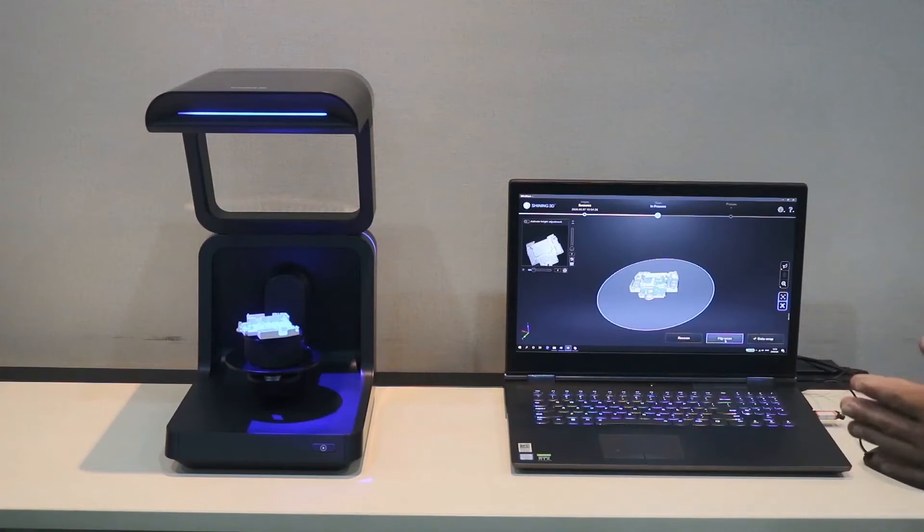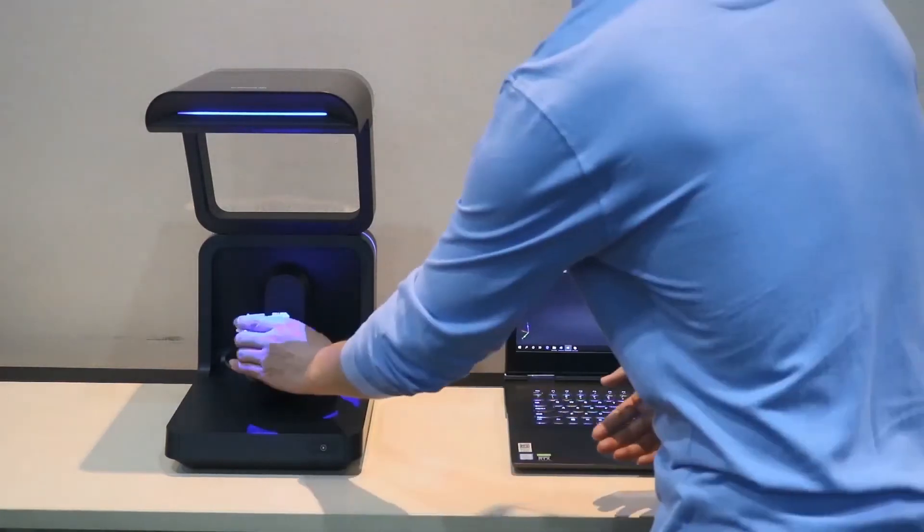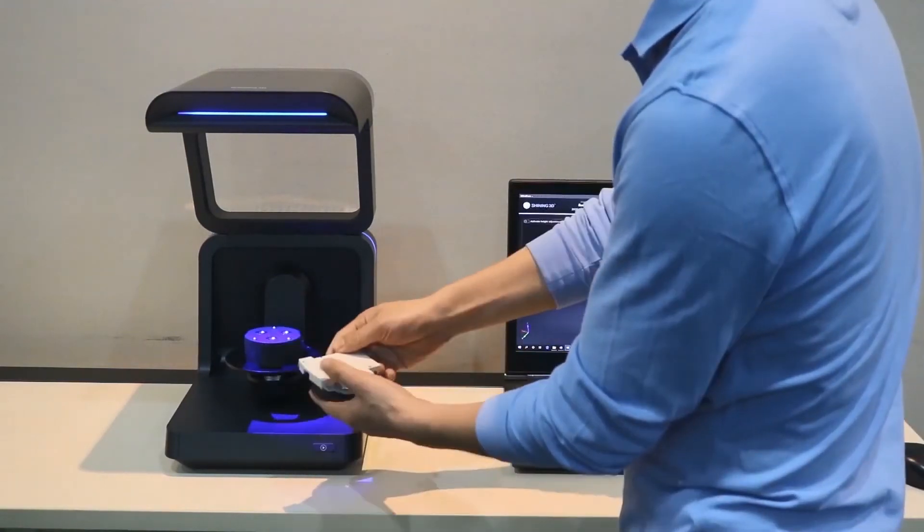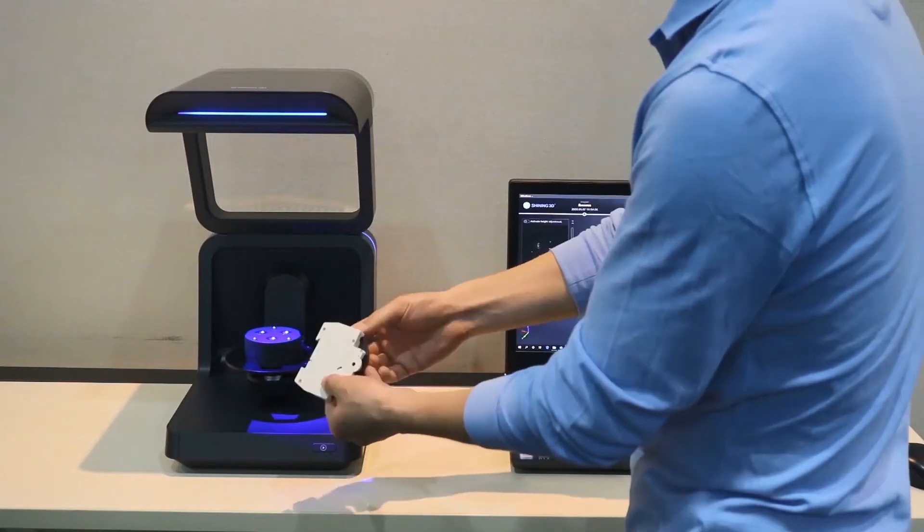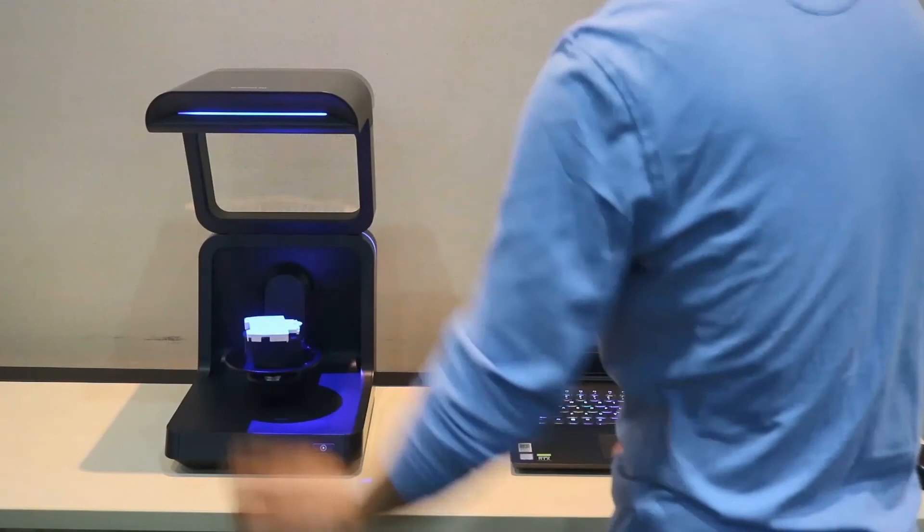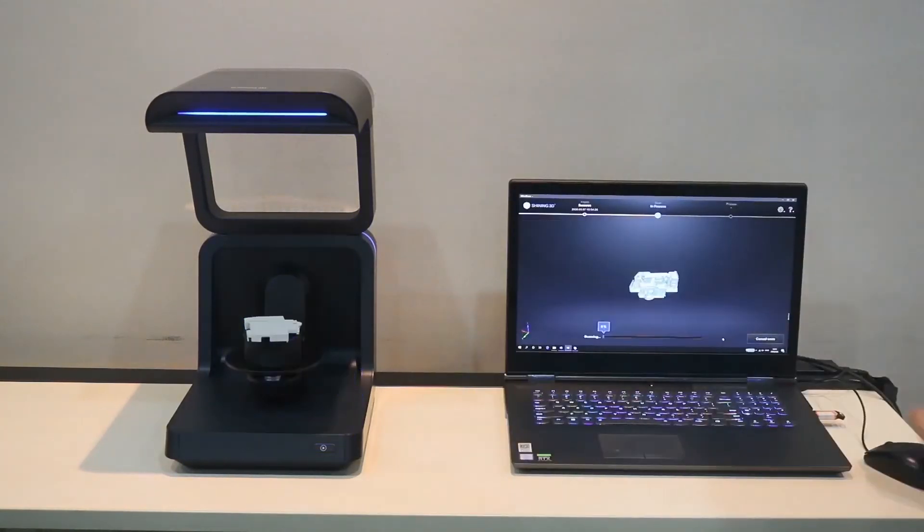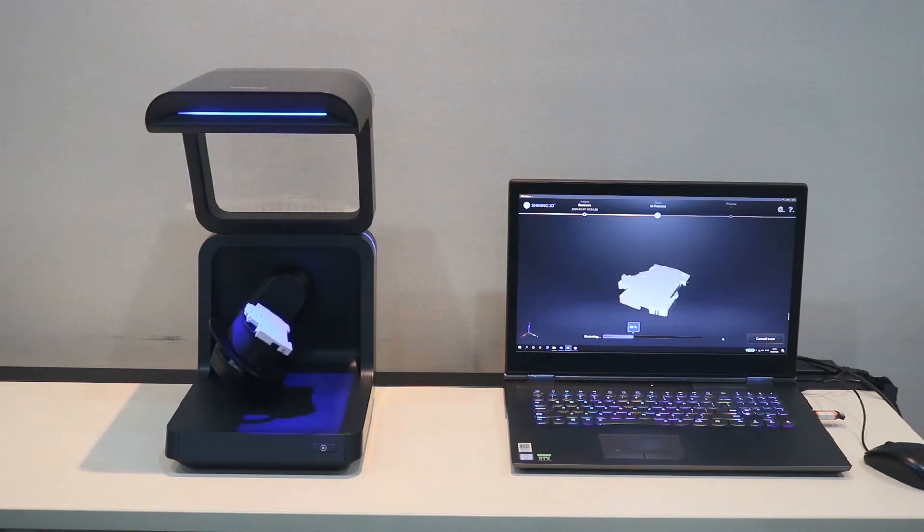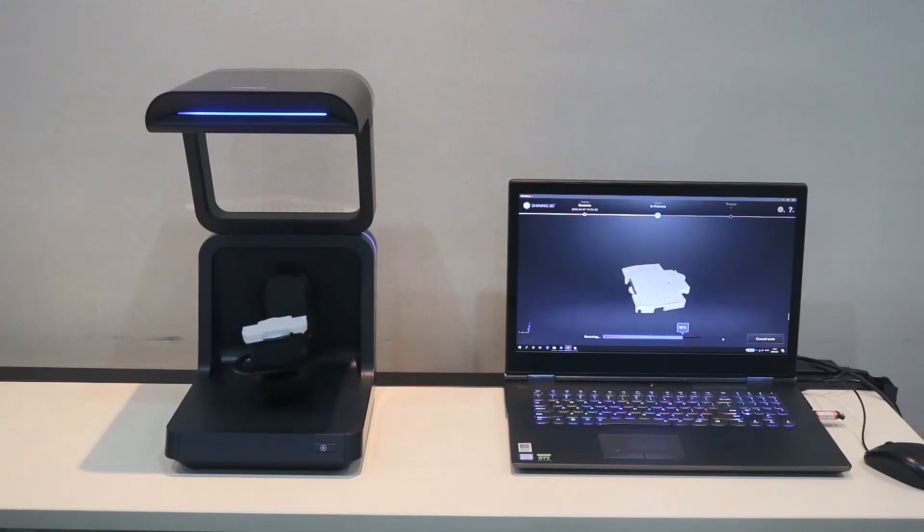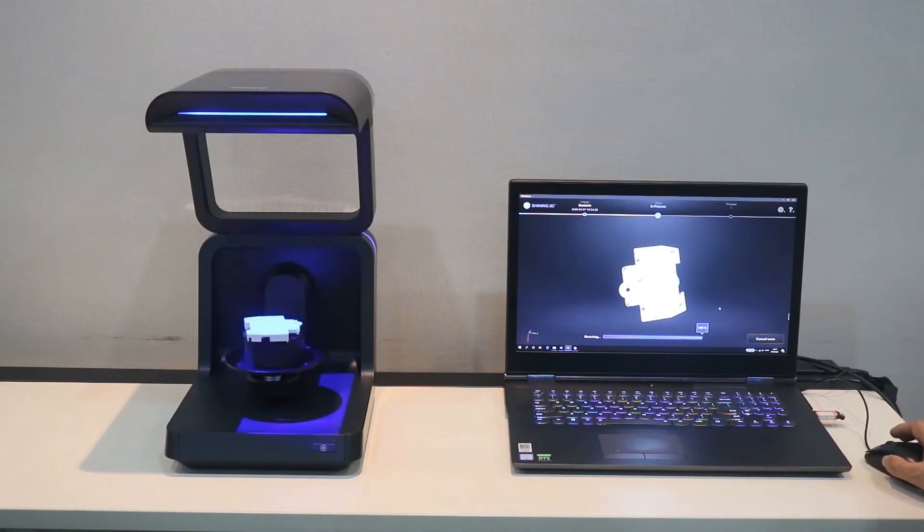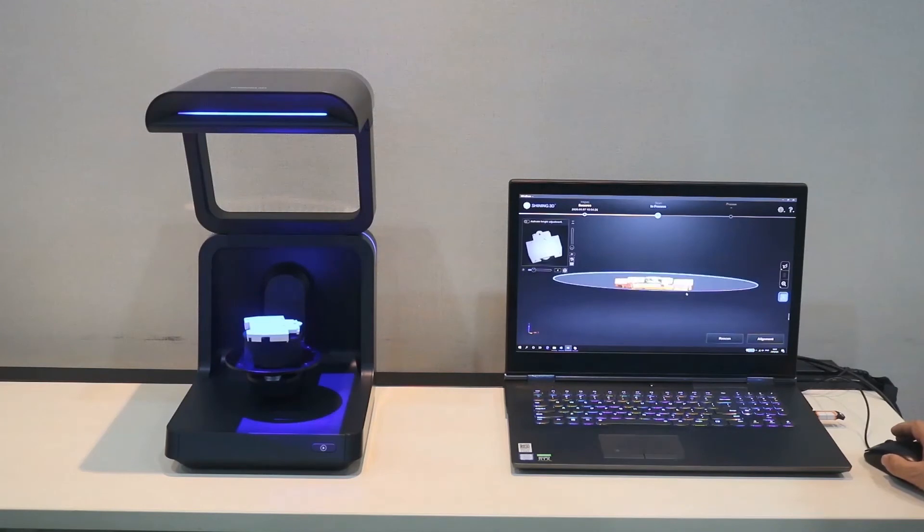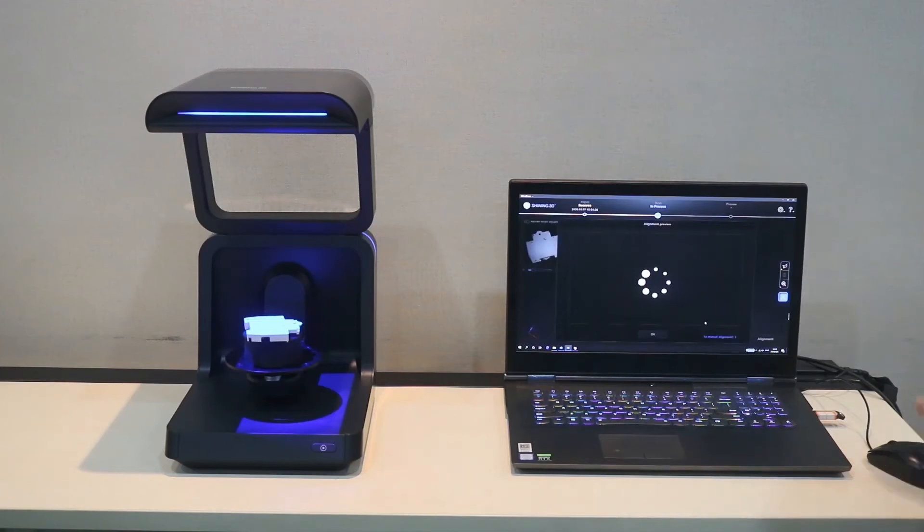It means that before we click the flip scan, we need to turn over the parts first. Like this. And then, put the parts on the turn table. And then, we can use the flip scan to scan again. The backside scanning is also finished. That's all. This one is complete. We need not to capture any other data.